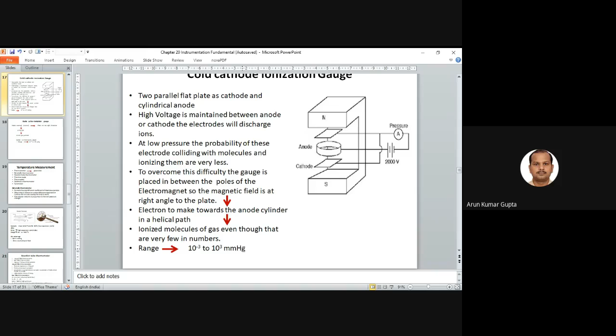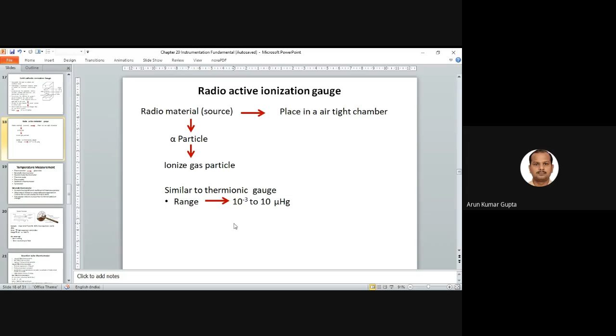So this is all working for very low pressure. Hot cathode ionization is for very low pressure, then the cold cathode is even higher. Then we have the radioactive ionization gauge. A radioactive material source is placed in an airtight chamber and emits alpha particles that ionize the gas particles. This is similar to the thermionic gauge, and it can measure around 10 to the power minus 3 to 10 micron Hg pressure.